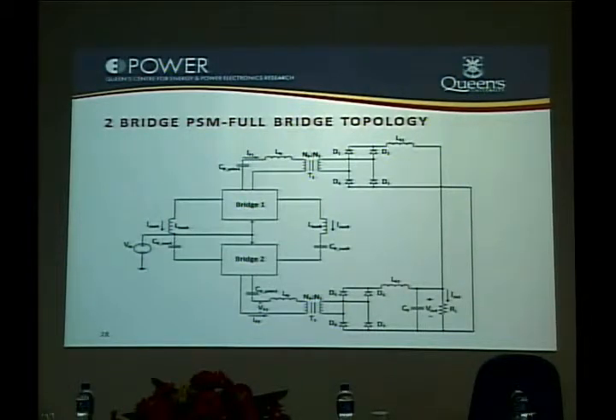As we've seen earlier, we can do phase shifting between the gating signals of the two bridges. Doing phase shifting between the two converters gives us circulating current, which helps us achieve zero voltage switching. This is the same principle - as a matter of fact, the first concept was developed here, and then we used the same concept on the inverter.